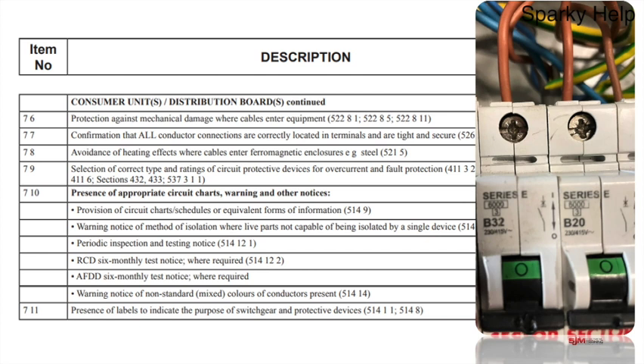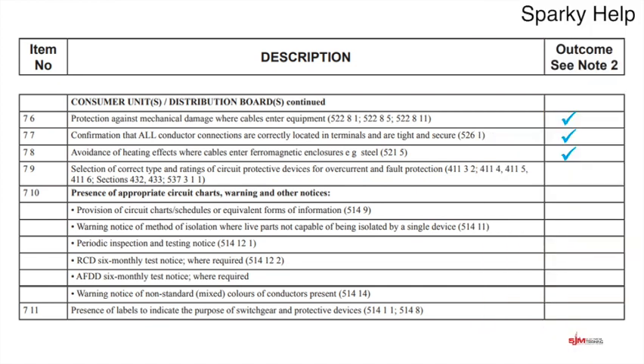It could be that the cable is correct and the breaker is wrong, or it's the cable that's wrong and the breaker is correct. But without further information, we're not 100% certain, unless you did the job in the first place, or you have the specification. Remember, in theory you've got all this information to hand. So that's the sort of thing you're looking out for. Hopefully it's going to be a tick.